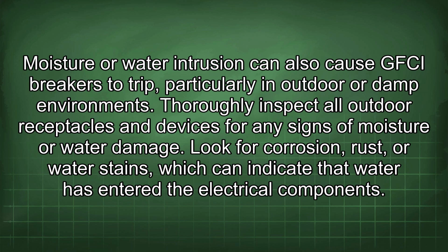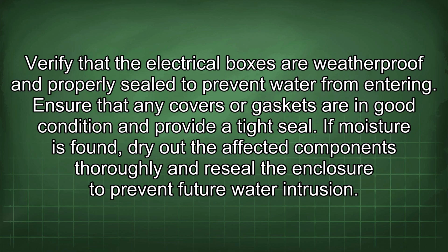Moisture or water intrusion can also cause GFCI breakers to trip, particularly in outdoor or damp environments. Thoroughly inspect all outdoor receptacles and devices for any signs of moisture or water damage. Look for corrosion, rust, or water stains which can indicate that water has entered the electrical components. Verify that the electrical boxes are weatherproof and properly sealed to prevent water from entering. Ensure that any covers or gaskets are in good condition and provide a tight seal. If moisture is found, dry out the affected components thoroughly and reseal the enclosure to prevent future water intrusion.